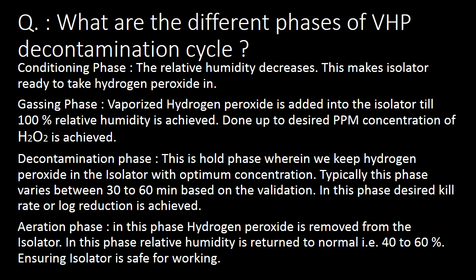The third important phase is the decontamination phase. This is the hold phase wherein hydrogen peroxide is kept in the isolator at optimum concentration. Typically this phase varies between 30 to 60 minutes based on validation. In this phase, the desired kill rate or log reduction is achieved.